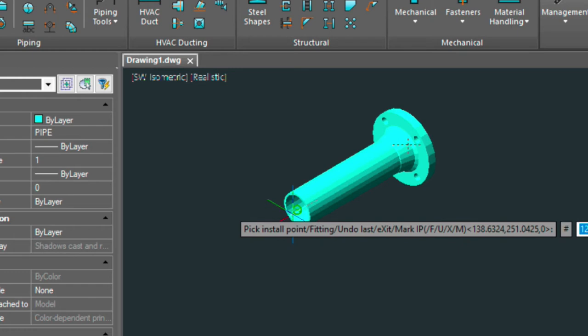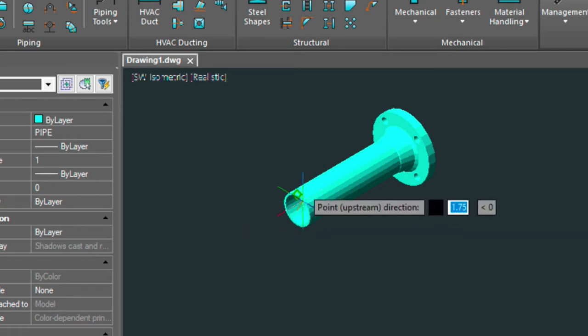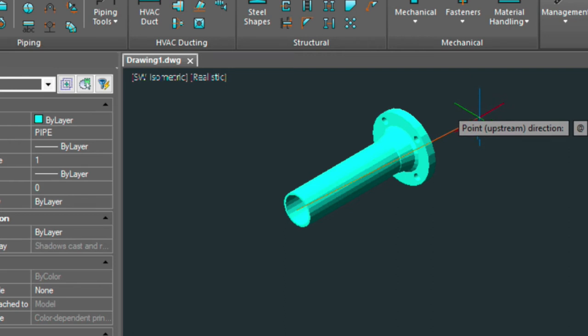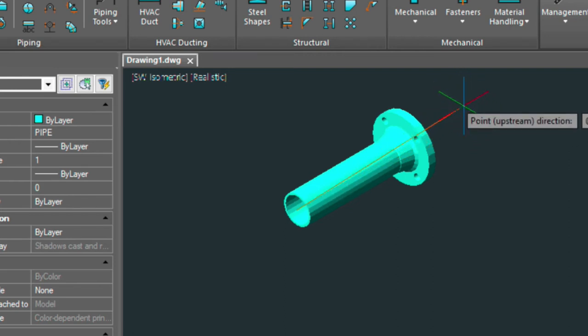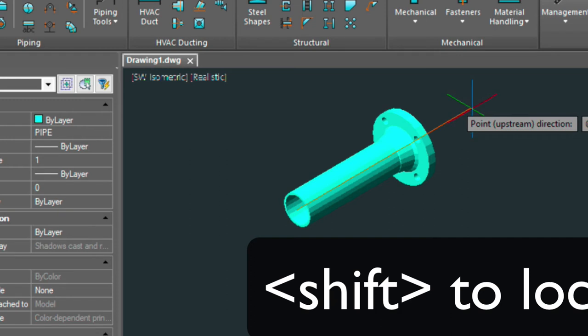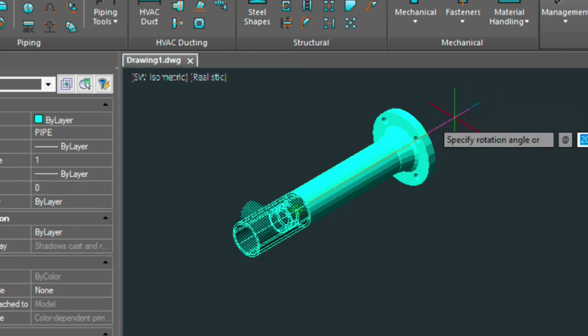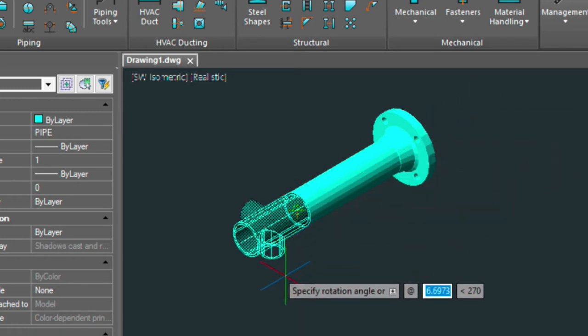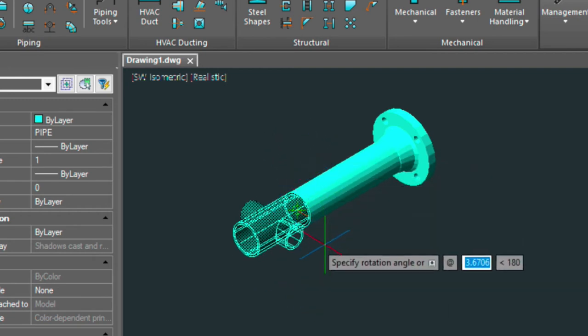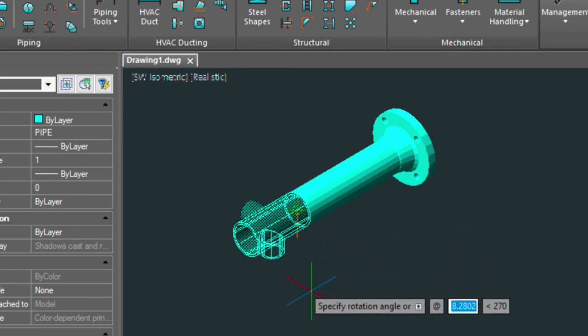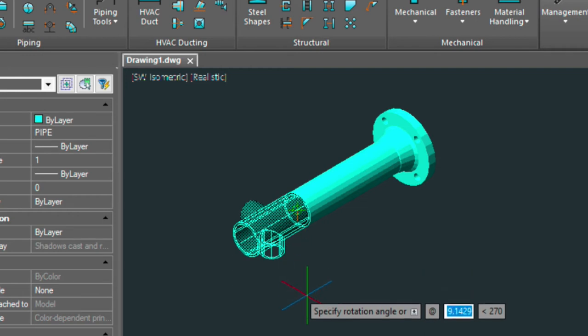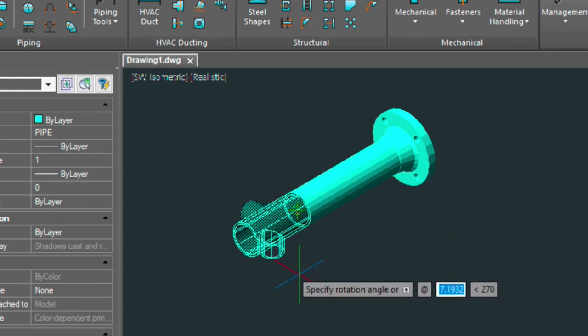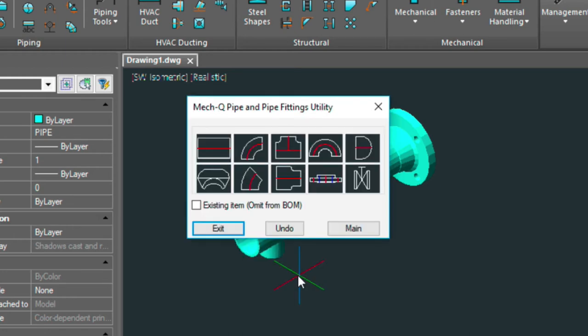It's giving us this error message because it wants us to finish out that flange but we don't want to. And then we don't want that last point either. We want to select a new point which is right here. And you can see the circle basically saying that's the center of the pipe. We just left click on that. We pick a point in the upstream direction. Now if your cursor is like mine where it doesn't want to snap into that angle, hold down your shift key on your keyboard and lock that in. Otherwise you're going to get a bad result. So lock that in and at the same time hold it down and then left click. So that basically allows us to rotate this T around that straight piece of pipe. So we want to rotate it down. And I'm just moving my cursor or my mouse up and down to get that rotation. And once I get it positioned then I left click. Then that puts the T in.